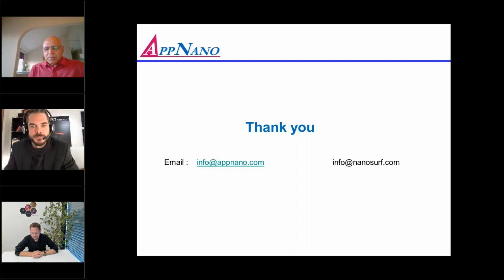Yeah. So there I can separate it in two parts. On the scan heads, it's compatible with the Flex AFM, the Core AFM, and of course with our new flagship, the Drive AFM. For the controllers, it works with the EasyScan 2 controllers, with the C3000 controllers, with the C3000i controller, and also with the new CX controller. For the EasyScan 2 and C3000 controllers, you will need a signal access module, as Ami has shown in his presentation. And for the CX controller and the C3000i, software options are enough to get the signal I/O activated. And then you can monitor temperature or thermal conductivity parallel to the topography.